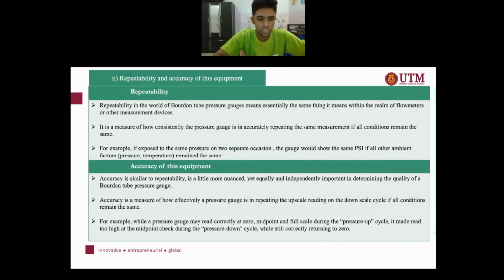And then accuracy of this equipment is similar to the repeatability. It's a little more nuanced, yet equally and independently important in determining the quality of a Bourdon tube pressure gauge. Second, accuracy is a measure of how effectively a pressure gauge is in repeating the upscale reading on the downscale cycle if all conditions remain the same. Last but not least, for example, while a pressure gauge may read correctly at zero, midpoint and full scale during the pressure up cycle, it may read too high at the midpoint check during the pressure down cycle while still correctly returning to zero. That's all.